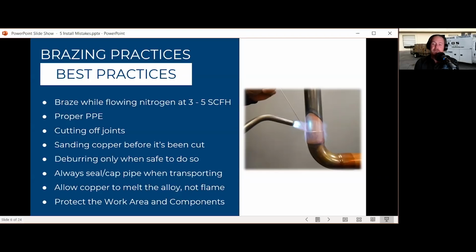Bert says there's a great video on HVAC School for how to flow. Yes, Bert has a video up on the HVAC School YouTube channel on how to flow nitrogen while brazing. And in fact, even before you flow, like we said, you need to purge first, because you have to get all of that air displaced before you even start to flow nitrogen. So purge it through first and then flow.